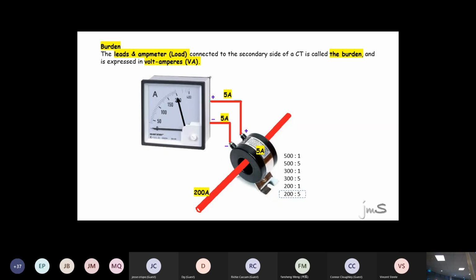Why is that? Because this ammeter is actually seeing 5 amps flowing in. So technically it's 5 amps showing. All they did was repaint and renumber the nameplate, so that when it goes to 5 amps, it actually shows 200 amps. How come you have not done that?